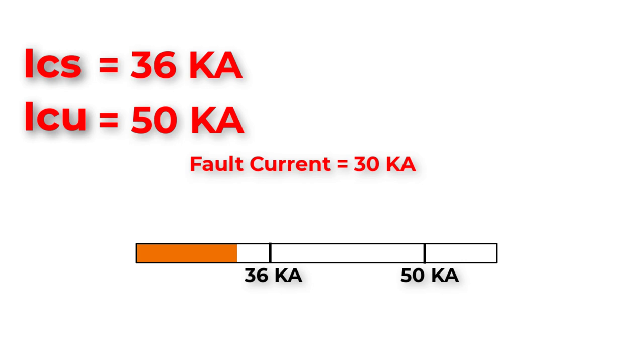But if the fault is equal to 45 kilo-amperes, for example, this fault current is above ICS and below ICU, so the breaker will handle this situation and will trip without any rupture, but we will have to replace this breaker.